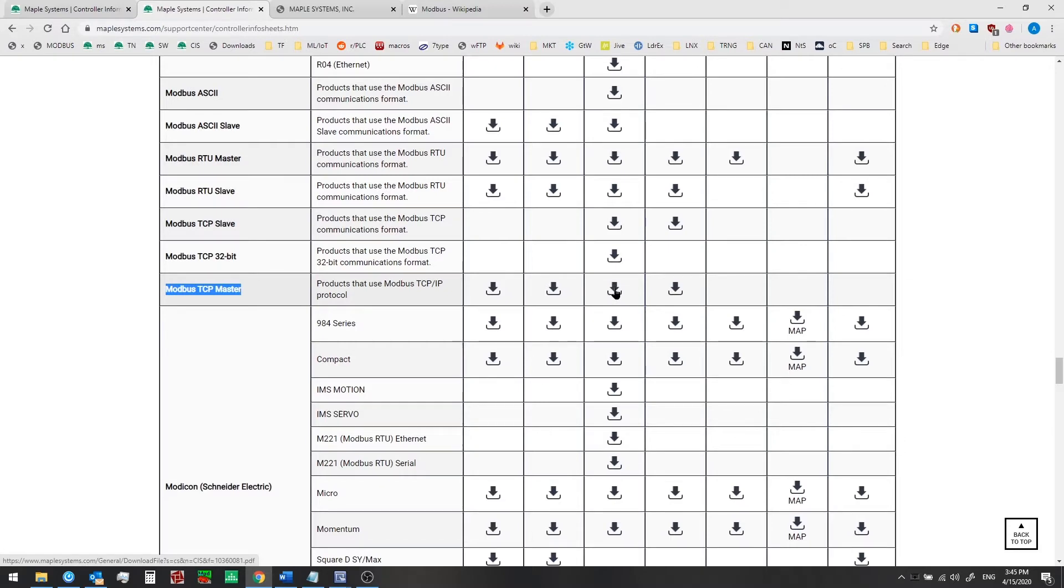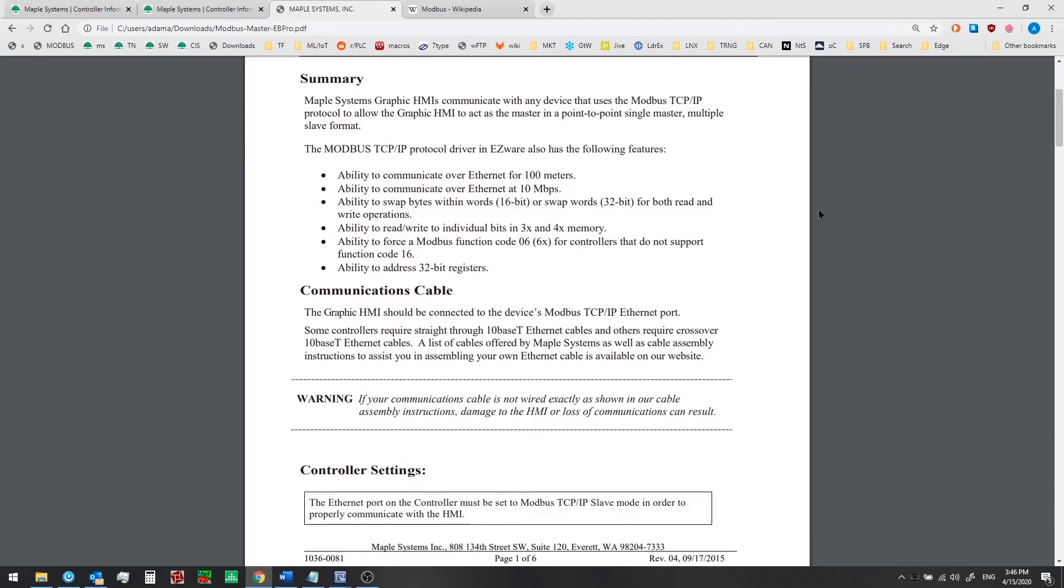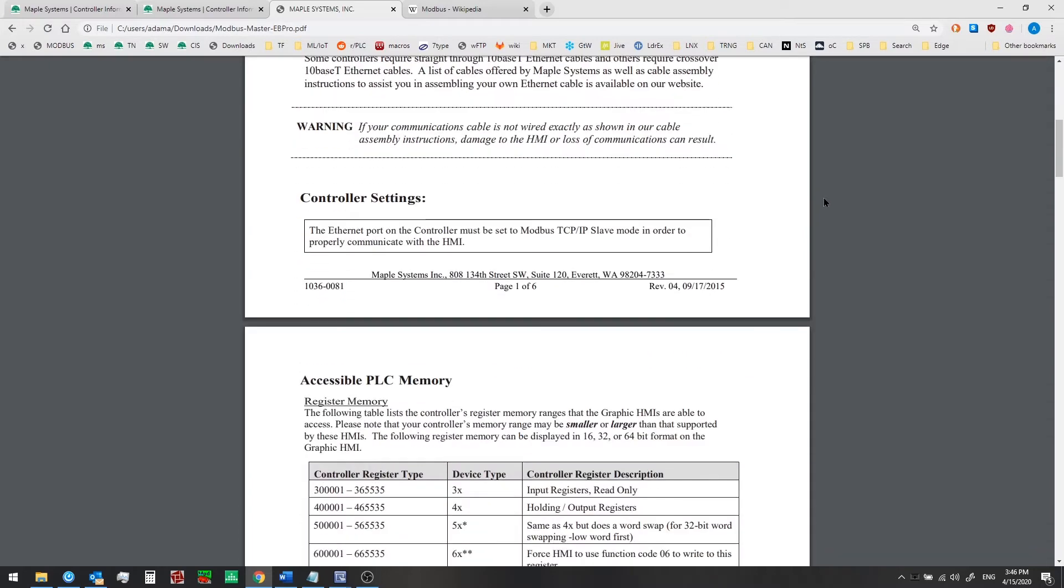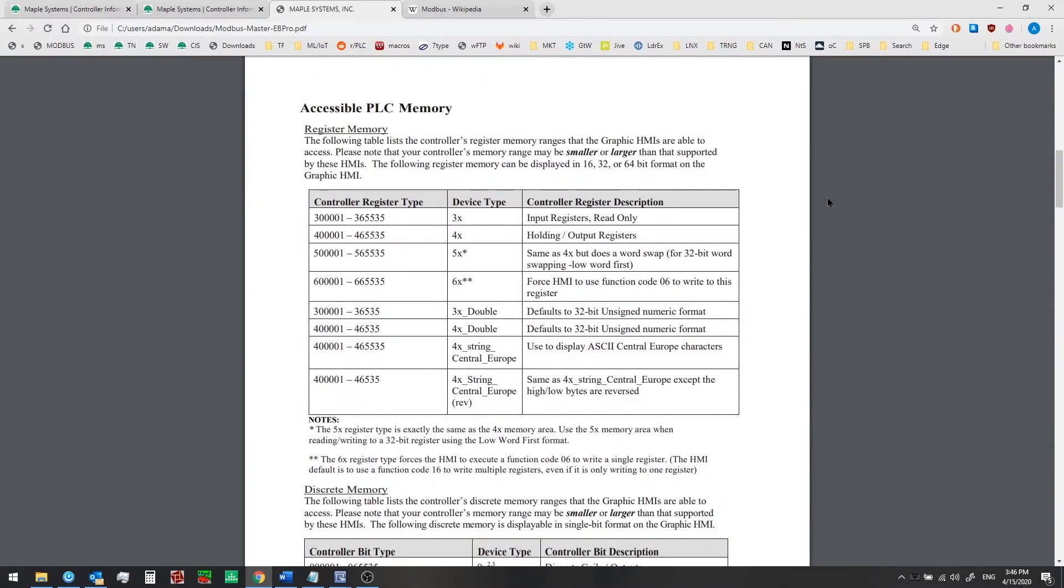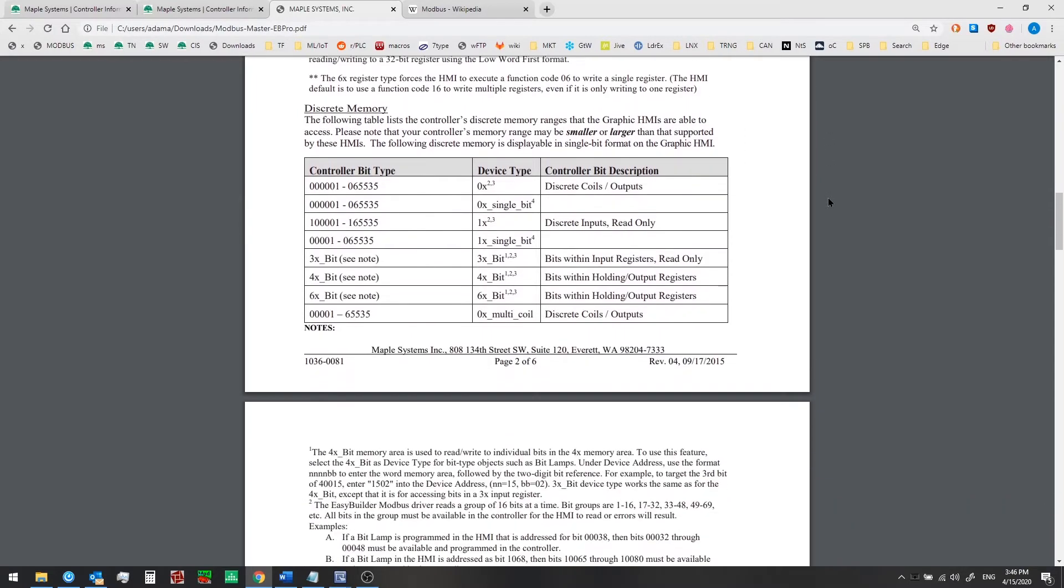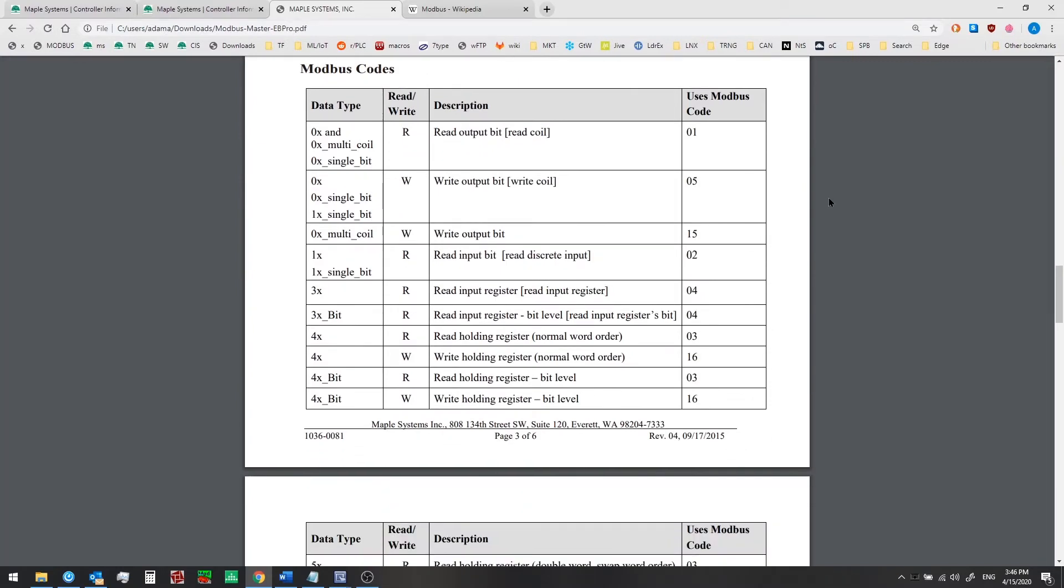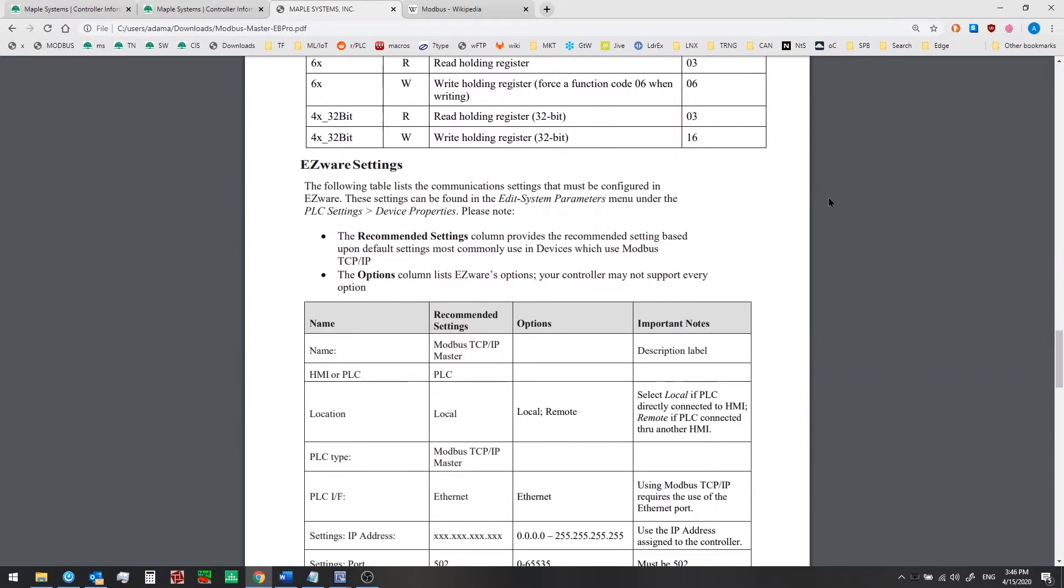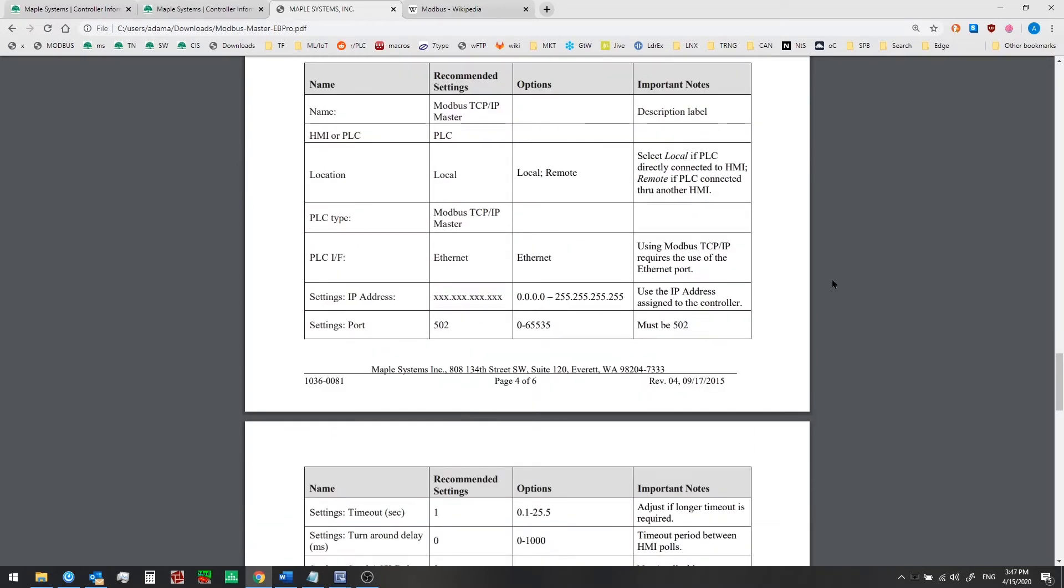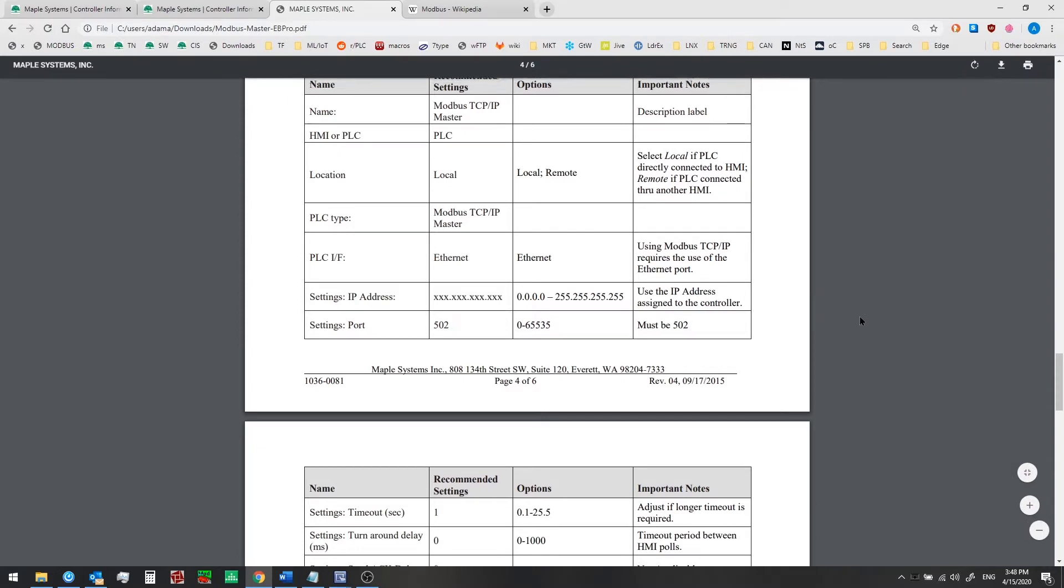The third column is the document that we need. This is our controller information sheet for Modbus TCP IP master. There's a number of things in this document. It talks about communication cables - it'll just be an Ethernet cable for this example. It talks about accessible PLC memory, register memory, and discrete memory, the Modbus function codes, and we also have some recommended settings for EB Pro. For example, the port number for Modbus should be port 502, and when we first add the driver in EB Pro it will already have that set.